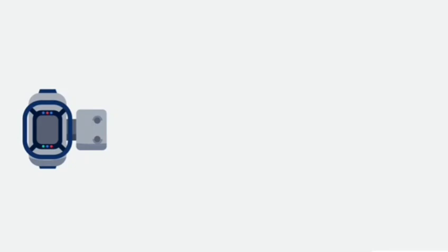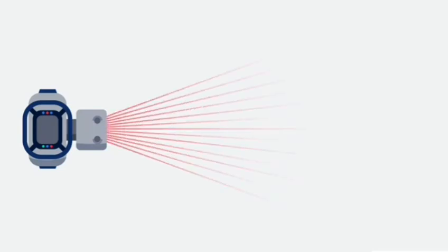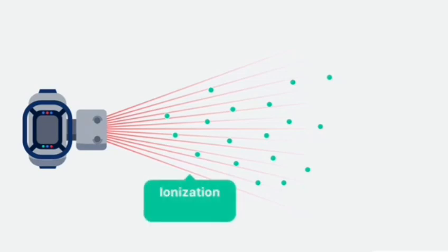To understand exposure, we have to understand ionization. When the X-ray beam passes through air or any form of matter, it will interact with air molecules and knock electrons out of orbit. This process is called ionization because ions or charged particles like free electrons have been created, and we measure these ionizations as exposure. So this is the key point. Exposure is a measurement that tells us the number of ionizations in air.